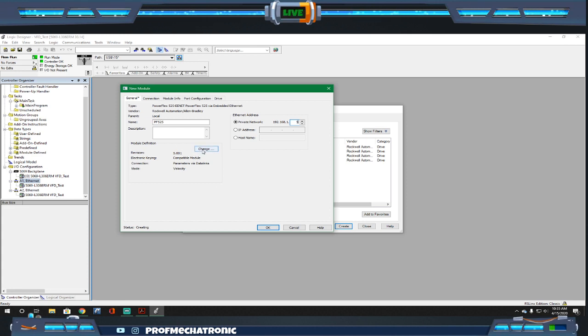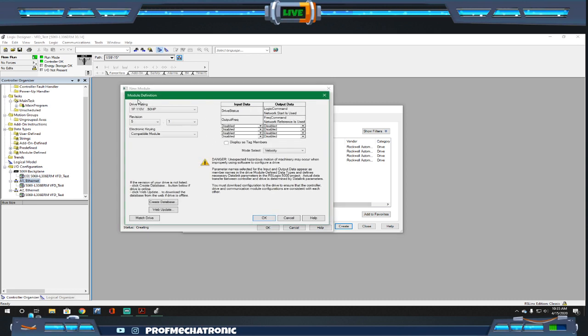From here, we also need to update and change our module definition. So if you remember, one of the important things that we saw in the RSLinx was the revision number. Now the revision number of this drive is revision number 1. So you have to make sure that this revision matches the drive that you're using, because without that, you won't be able to have the communications. As we do firmware updates, things change and things need to be updated. So you want to make sure that your revision number matches here.